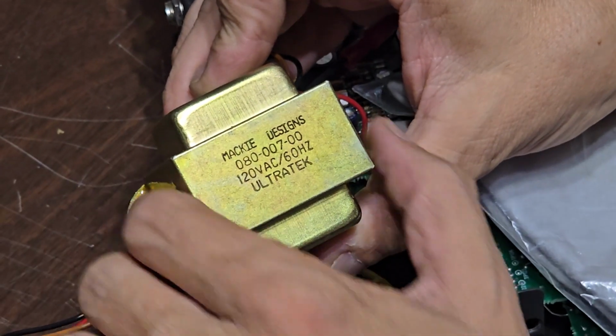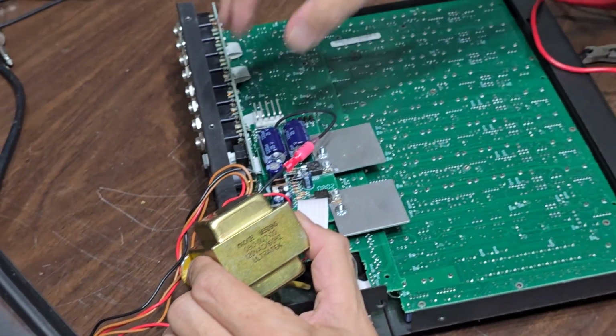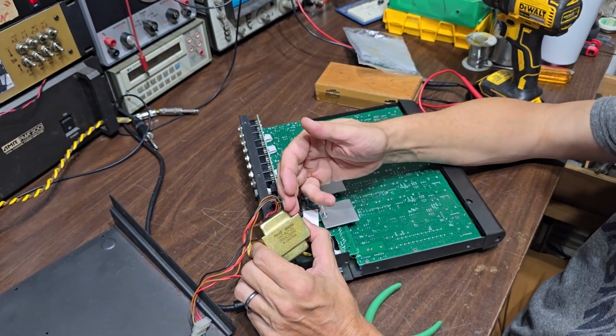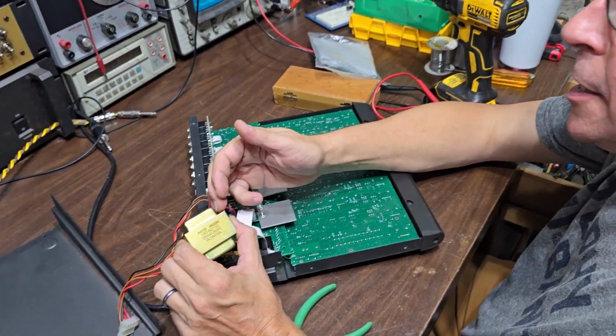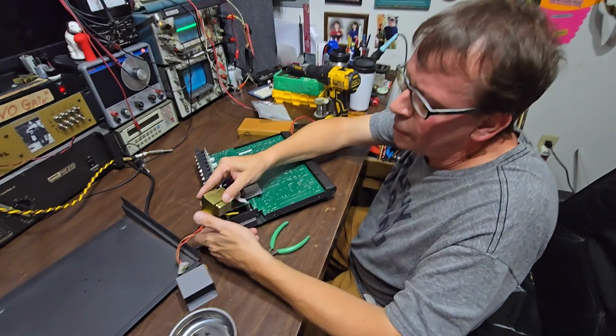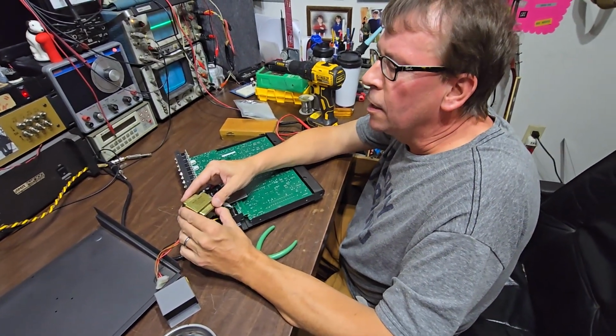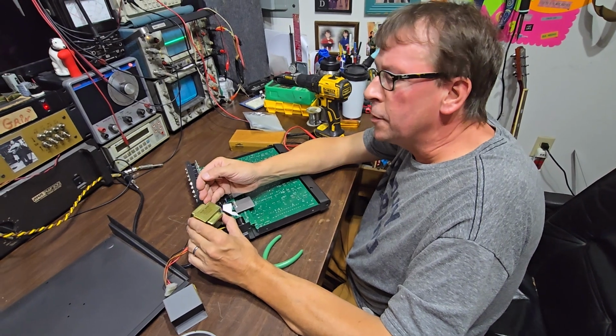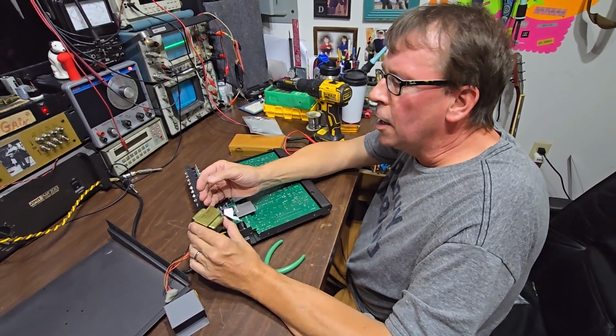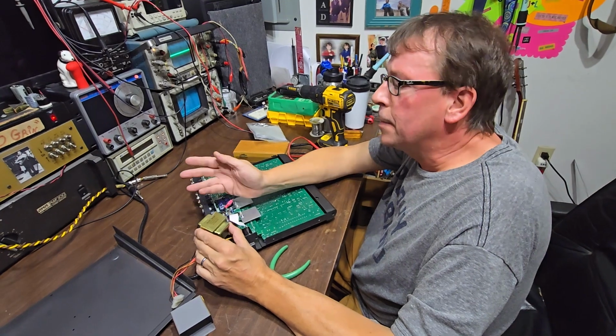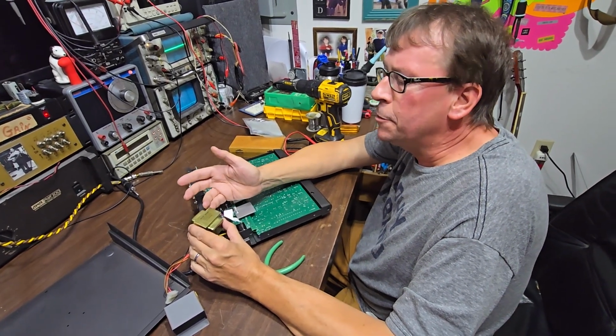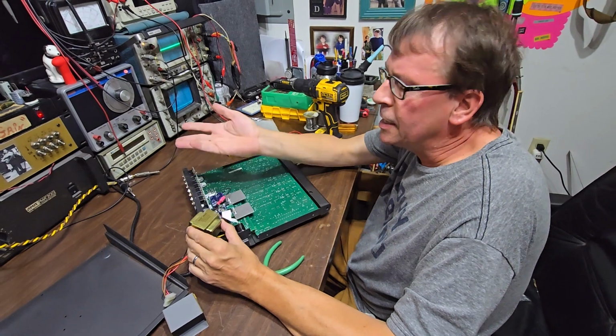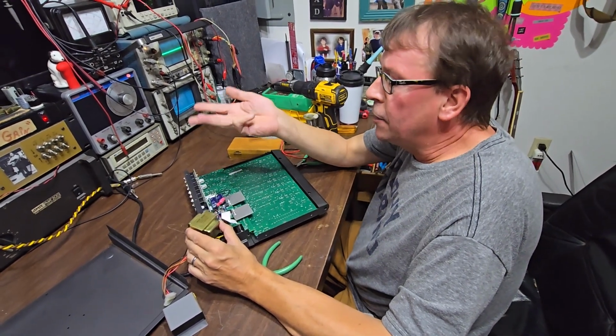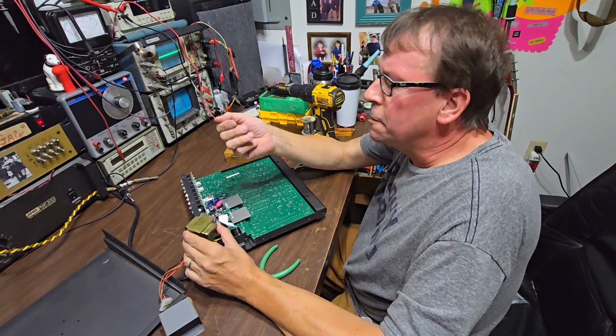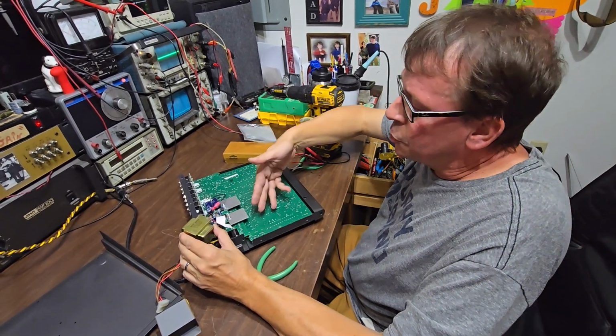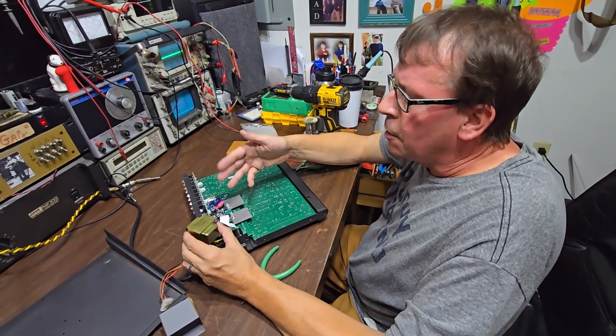Now, the fact that the primary is open tells me one of two things. Since that primary is open on this transformer for sure, then we know that it either has a thermal fuse on the inside that's failed and no longer resets, or it has a one-shot fuse, which is real common in cheap transformers. A one-shot fuse opens and then that's it. You replace it if it goes bad. Now the other thing is, what took it out in the first place? There's a chance that there was a short in the circuit somewhere that took the transformer out.